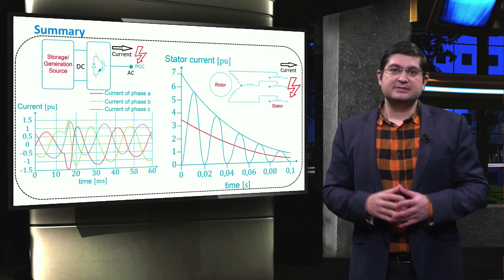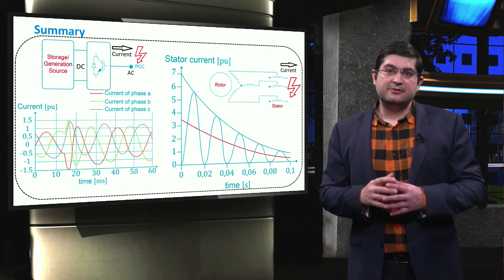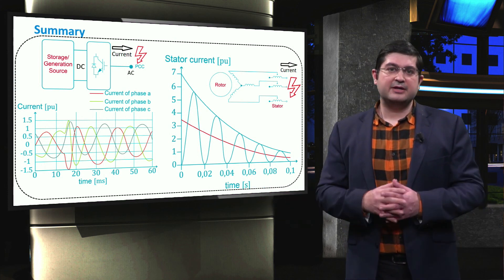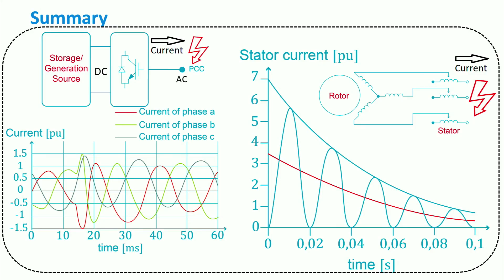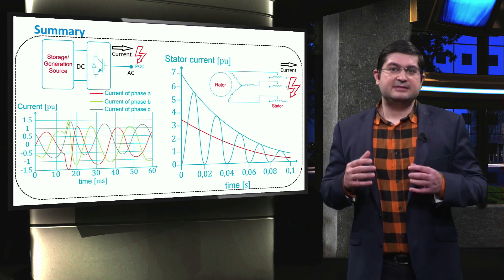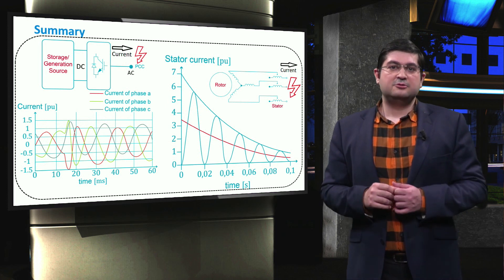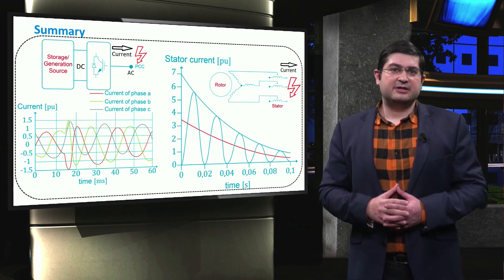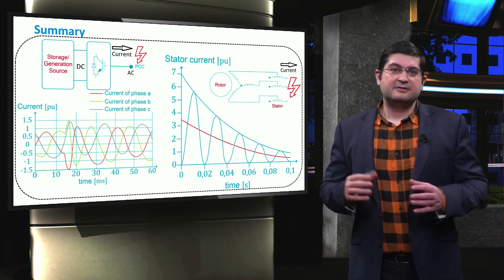In summary, we addressed the behavior of two types of distributed generators with and without power electronic interfaces. We discussed that distributed generators based on electrical machines will become unstable if the fault clearing time is greater than the critical clearing time. Moreover, we compared the fault current of these two types of electrical components. The large contribution of electrical machines to the fault current facilitates fault detection, though the low contribution of components using power electronic interfaces makes it difficult to detect faults in microgrids.